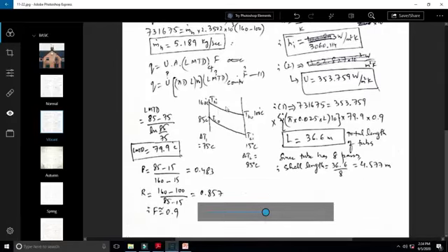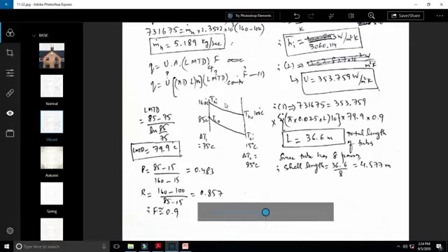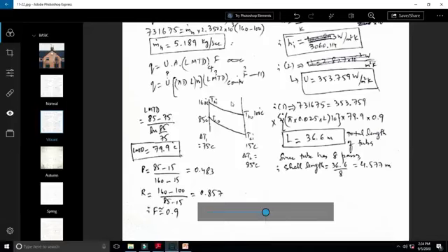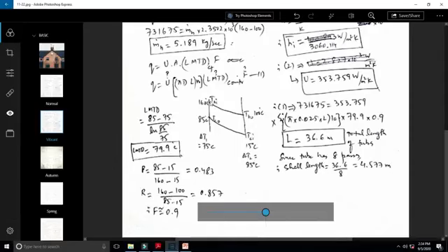So we will make the figure of a counterflow heat exchanger. Although for some of the tubes it would be counterflow, and for some of the tubes it would be parallel flow, as I had explained in the theoretical part. And that is why we introduce a correction factor, which will take care of both the flows. So T hot in, T hot out, this would be the direction of flow of the hot fluid, and this would be the direction of flow of the cold fluid.